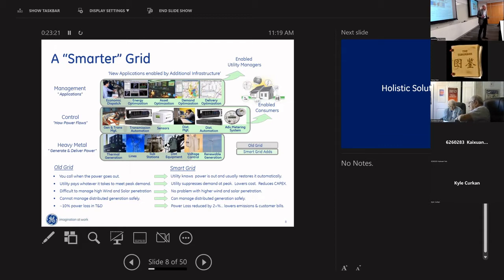Voltage control, for instance, we've been doing for a long time because voltage is directly proportional to load. If you're a summer peaking utility, like many are, and contracted to buy electricity, if you exceed your previous peak there's a severe financial penalty. We would put logic in your system so that if you approached your previous peak on a hot summer day, lowering the secondary voltage lowers the load. And we would do power factor control separately—switching capacitor banks on distribution feeders to reduce losses.